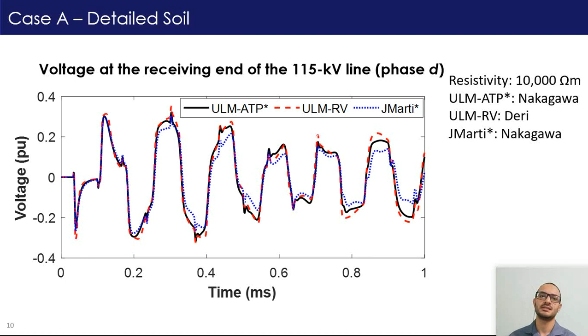We can observe that the voltage waveform calculated with JMarti star is similar to the other ones at the beginning until around 0.2 milliseconds. And as time runs, it presents greater deviations. This is related to loss of accuracy associated with the use of a real and constant transformation matrix. This simplification becomes more critical in this particular case because the effect of frequency-dependent ground parameters is stronger for high resistivity soils. So, the use of ULM-ATP star is recommended in this case.